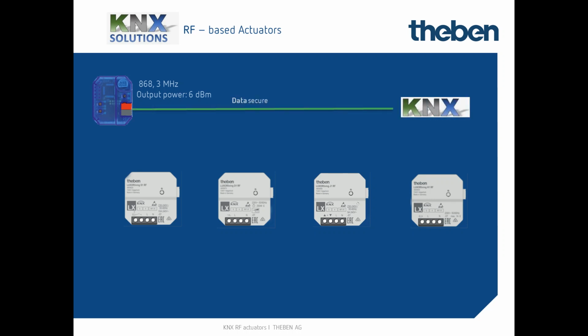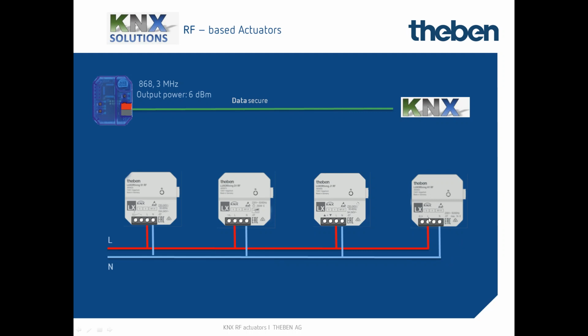So in regard of the powering of the actuators, I have to tell you the following: all these flush mounted actuators - switching, dimming, shutters and blinds, and heating - due to the fact that they communicate via remote, they need power because from the bus side, the KNX side, they can't be powered. So we need 230 volts to give them the power to operate.